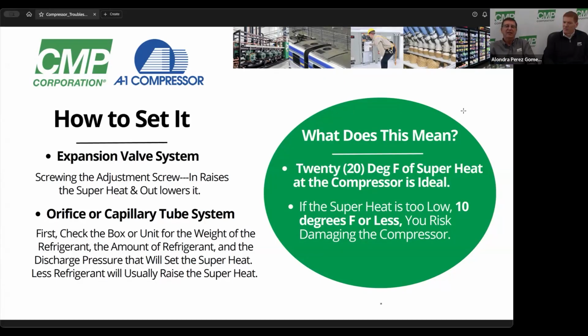Superheat means that you don't have any liquid entering your compressor. It sounds stupid, but a compressor is exactly what it is. It's a compressor. It's not a pump. Pumps will pump liquid. You've got water pumps, oil pumps, gas pumps, and they pump liquid. But compressors will only pump vapor. You can put vapor in a compressor and run it at 500 psi. But if you have zero superheat, which means you have liquid entering your compressor, then you're going to find out that that liquid could be 25,000 psi. And when you do that, parts are going to break because it's a compressor and it's supposed to compress a vapor and not try to compress a liquid, which you can't do.